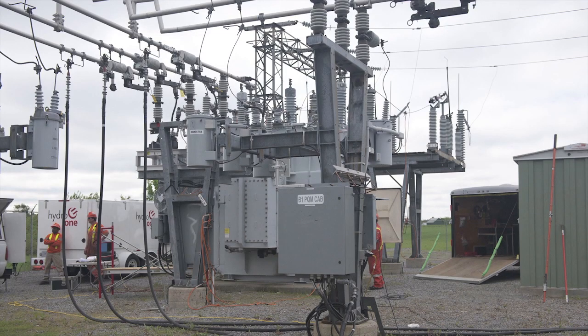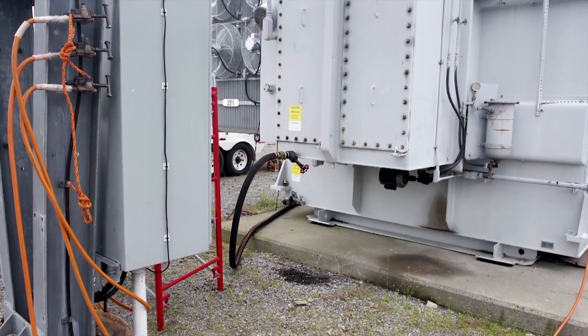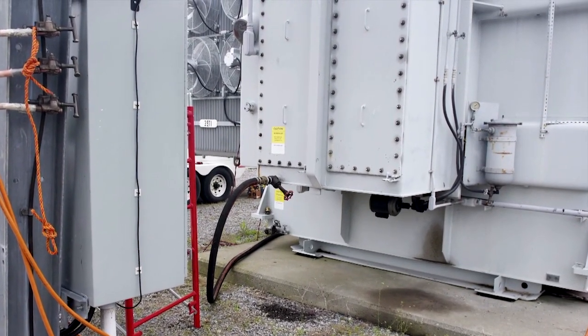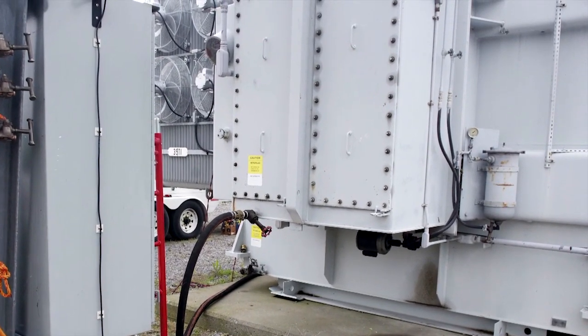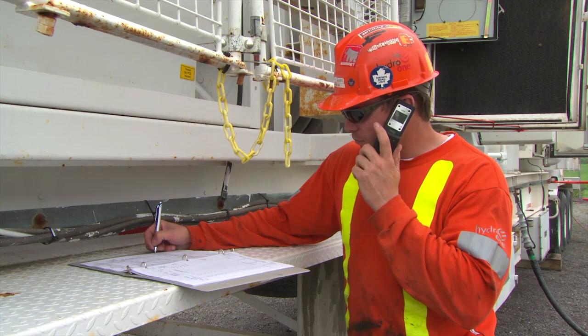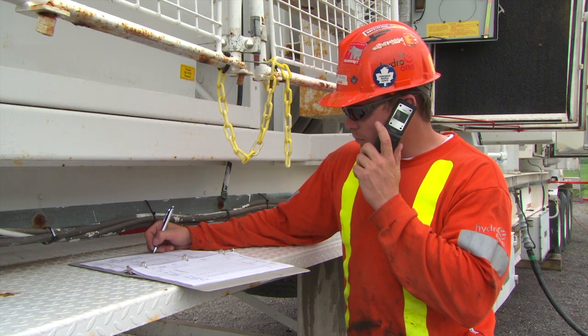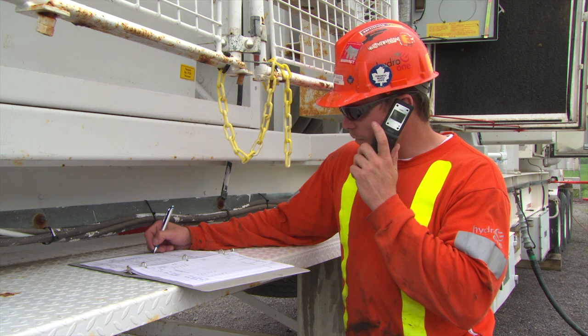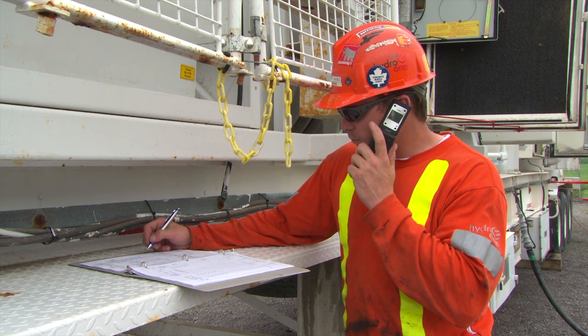Ensure that tools and equipment are clear, all connections have been made, and switchgear is in the proper position. If a capital project has taken place, ensure that all commissioning has been completed and perform phase checks. Call the controlling authority to inform them that the work permit has been surrendered on the DS and that it will now be switched into service.